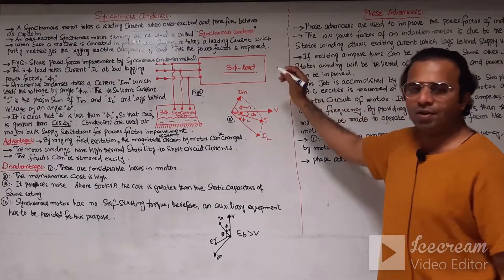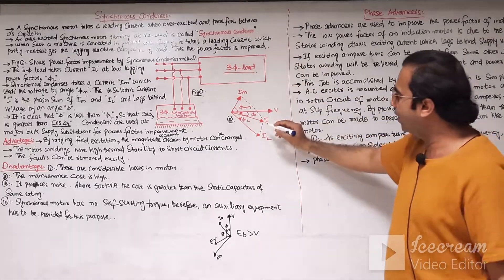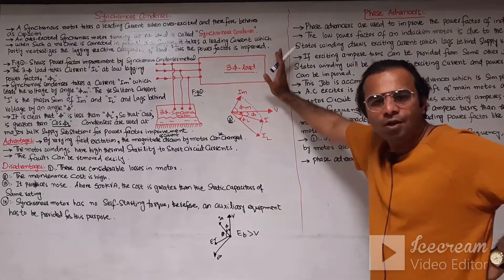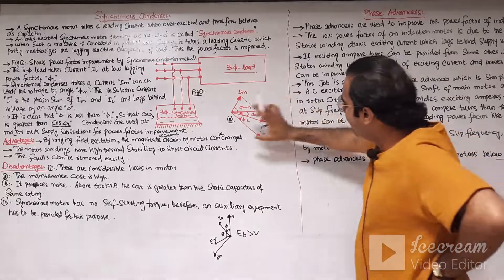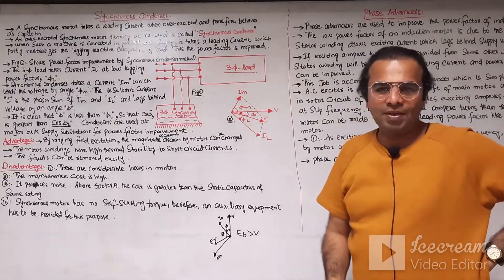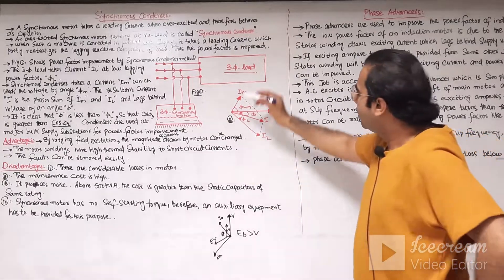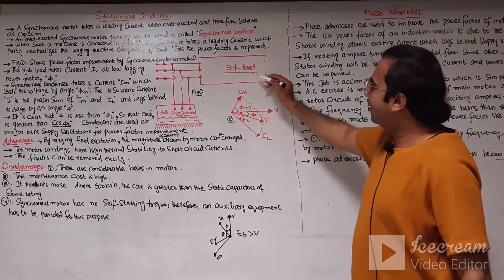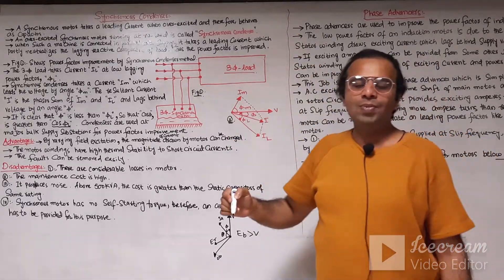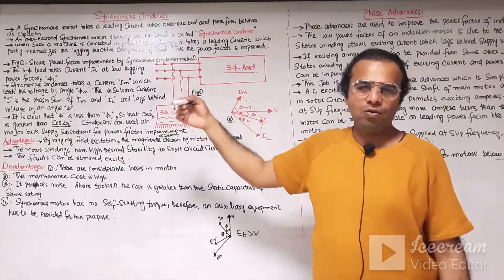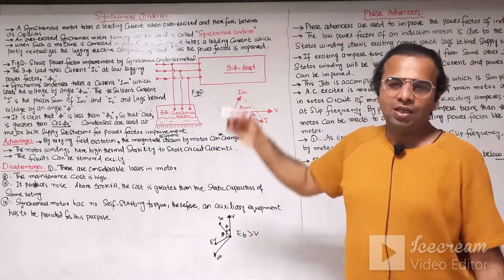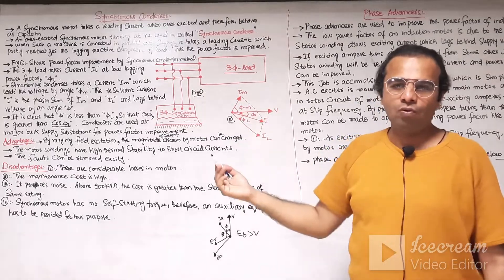Now let us discuss the power factor improvement method through the synchronous motor. An overexcited synchronous motor running at no load is called a synchronous condenser. When this synchronous motor is running at no load, it behaves like a synchronous capacitor or synchronous condenser. It takes a leading current from the main source and neutralizes — partly or completely — the lagging reactive component of the load, and hence the power factor of the three-phase inductive load is improved.